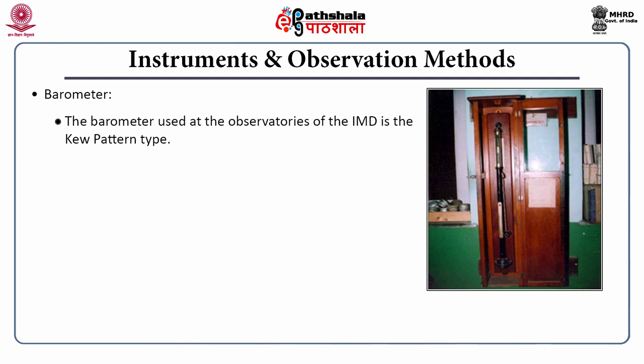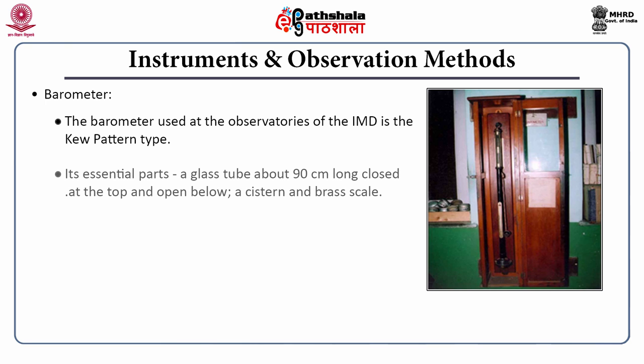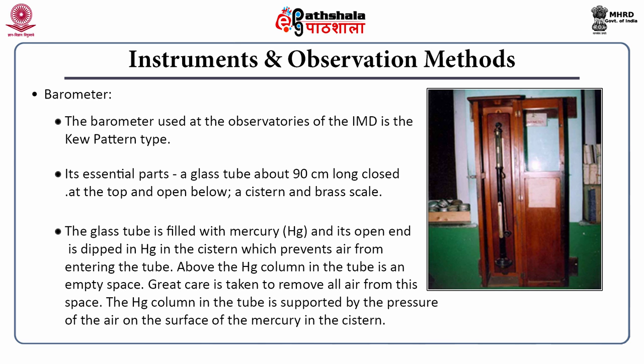The next equipment is the barometer, used to measure air pressure. In most IMD observatories, the Kew-pattern type barometer is used. Its essential part is a glass tube about 90 centimeters long, closed at the top end and open at the bottom. There is a cistern and a brass scale. The glass tube is filled with mercury and its open end is dipped in mercury in the cistern, which prevents air from entering the tube. Above the mercury column in the tube is an empty space, and care should be taken to remove all air from this space. The mercury column in the tube is supported by the pressure of the air on the surface of the mercury in the cistern.